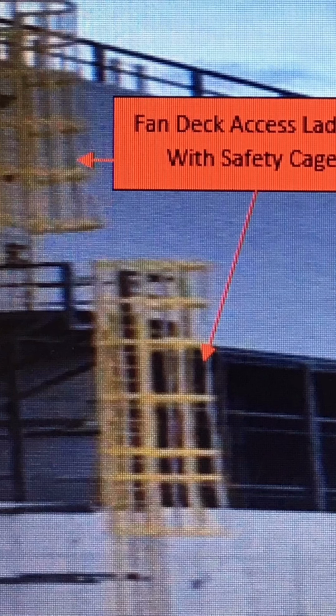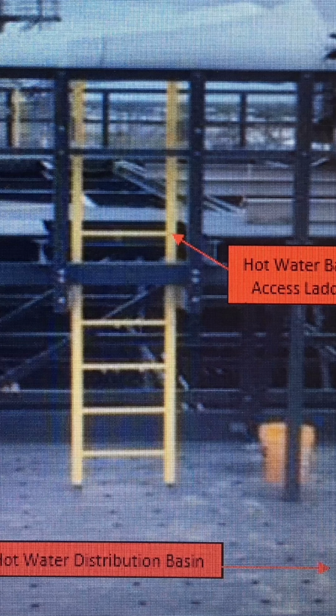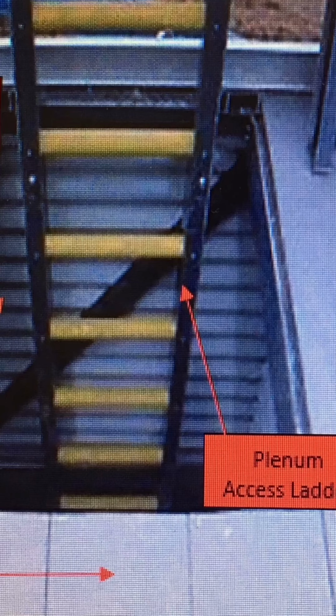A fan deck access ladder provides access to the fan deck from the ground level. Fan deck access ladders will typically be equipped with a ladder safety cage and will not require additional fall protection. Hot water basin access ladders provide access from the fan deck to the hot water basin. Hot water basin access ladders are typically short ladders and will not require fall protection if less than 6 foot.